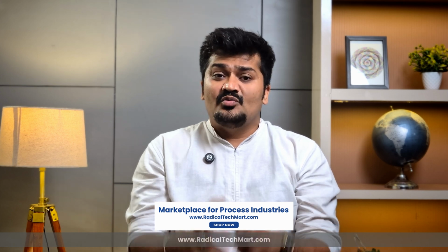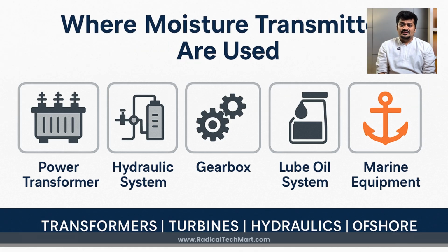Now, let's understand where it's used. You will find this transmitter installed in, first, power transformers to ensure dielectric safety. Second, hydraulic systems like injection molding, aerospace and presses. Third, gearboxes and turbines to prevent failure due to water ingress. Fourth, industrial lubrication systems for compressors, spindles or blowers. Fifth, offshore and marine equipment, where moisture contamination is common. In mission critical systems, moisture monitoring isn't optional.